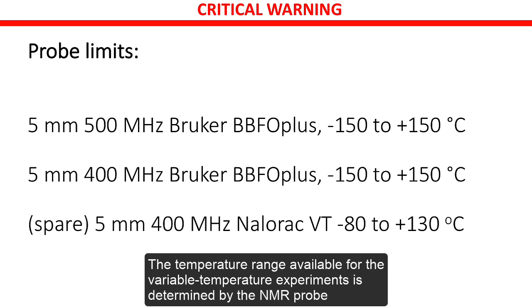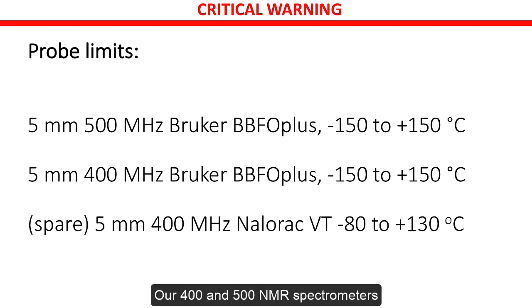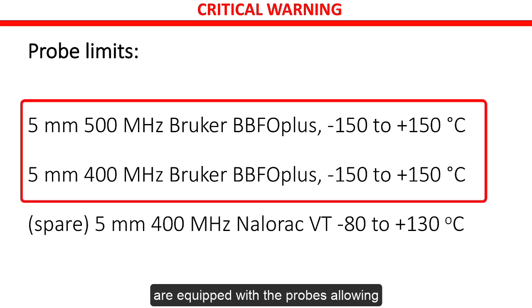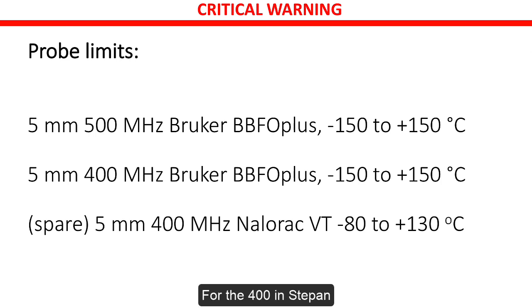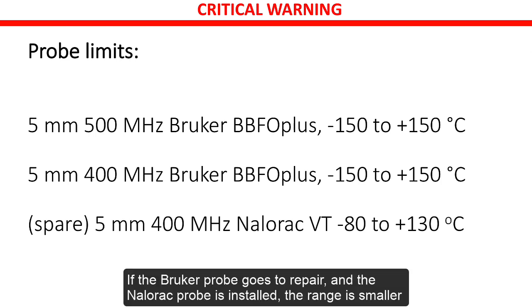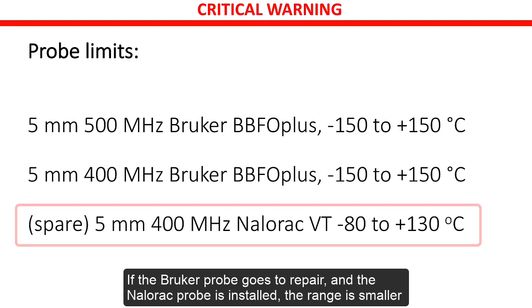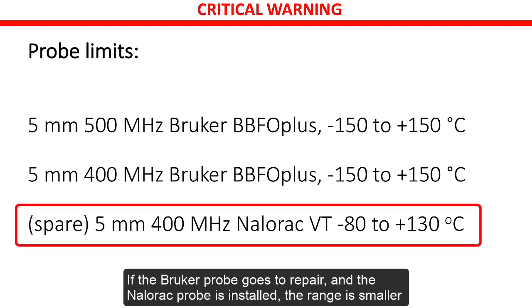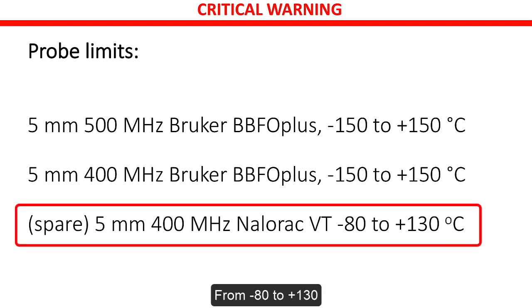The temperature range available for variable temperature experiments is determined by the NMR probe. Our 400 and 500 NMR spectrometers are normally equipped with probes allowing the range from minus 150 to 150 degrees C. On the 400 in Stepan, if the Bruker probe goes to repair and a Nalorac probe is installed, the temperature range is smaller, minus 80 to 130.